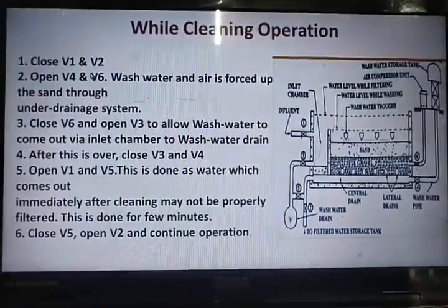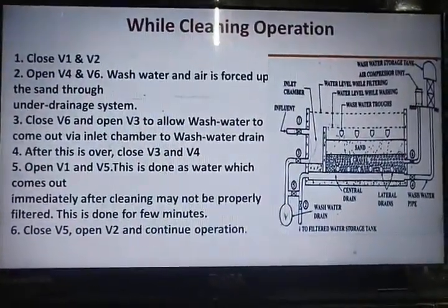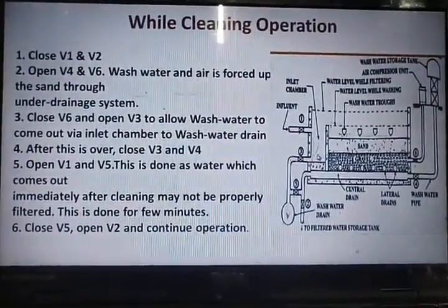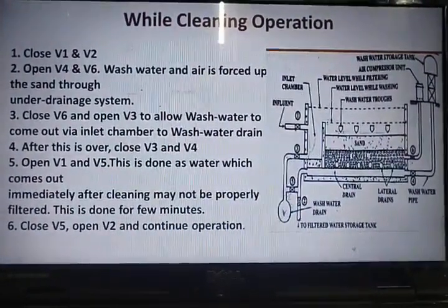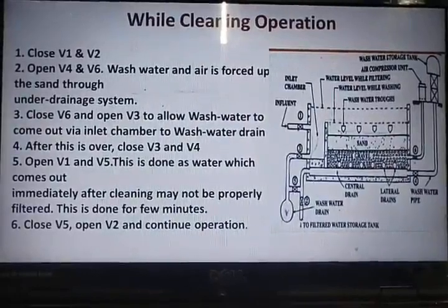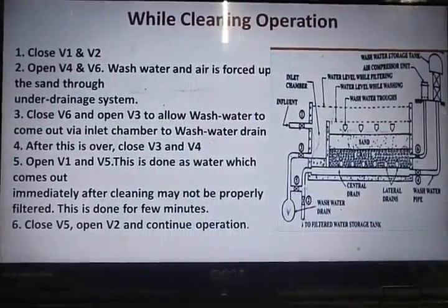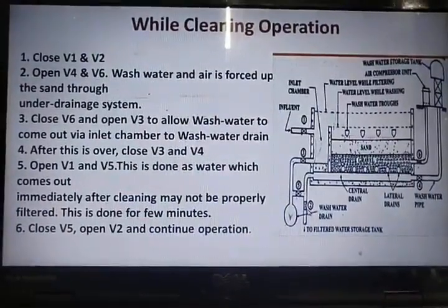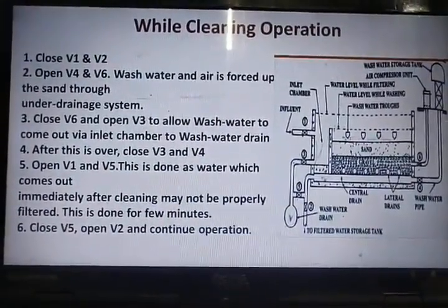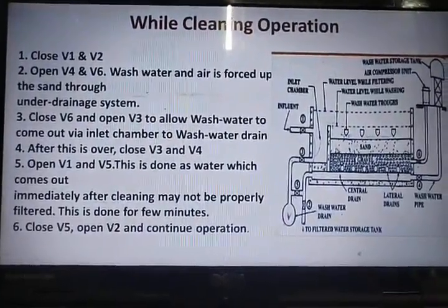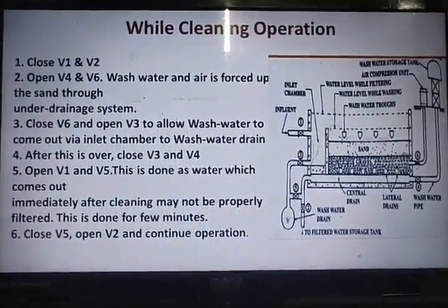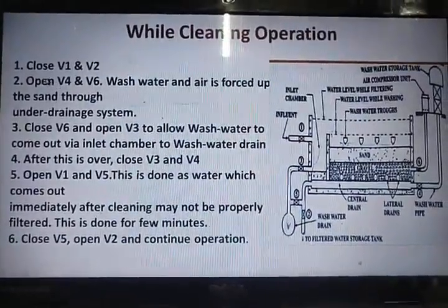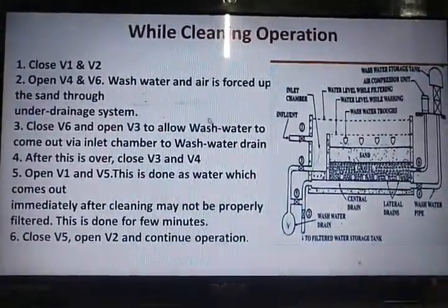Okay, so during normal operations of the filter, the water will be allowed through valve V1, and the treated water will be taken out through this central manifold by opening the valve V2. Only valve V1 and V2 will be open during the normal cycle of operation, that is during the treatment of water using filtration method. Okay, now while cleaning, we have to first close valve V1 and V2.